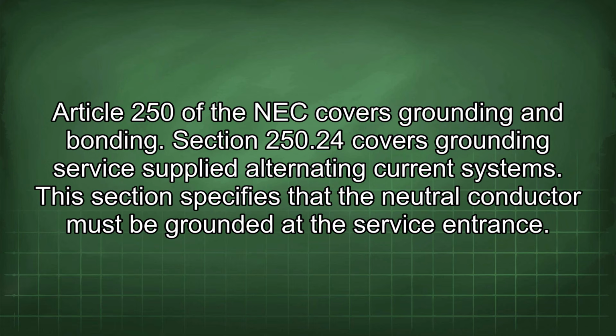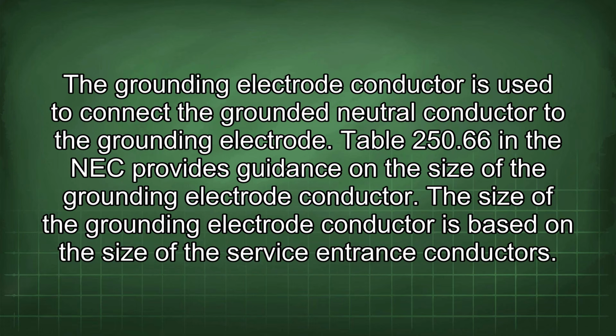Section 250.24 covers grounding service supplied alternating current systems. This section specifies that the neutral conductor must be grounded at the service entrance. The grounding electrode conductor is used to connect the grounded neutral conductor to the grounding electrode. Table 250.66 in the NEC provides guidance on the size of the grounding electrode conductor. The size of the grounding electrode conductor is based on the size of the service entrance conductors.